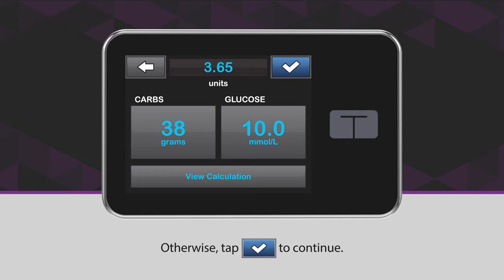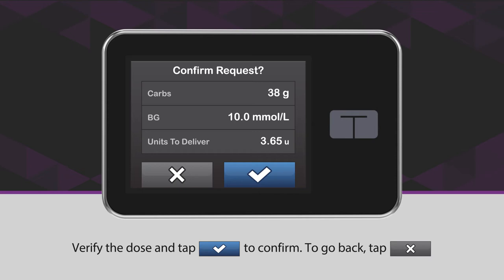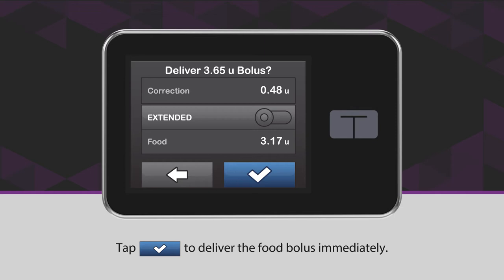Verify the dose and tap the blue checkmark icon to confirm. To go back, tap the X icon. Tap the blue checkmark icon to deliver the food bolus immediately.